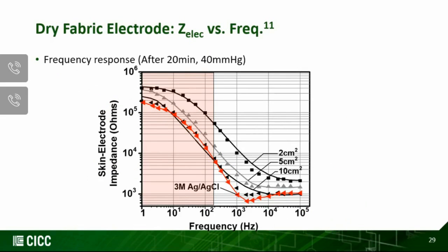Fortunately, the frequency response shape is similar to that of the 3M electrode. However, the fact that there will be much higher skin electrode impedance for the same area is still there. And this was measured after 20 minutes for initial stabilization time.